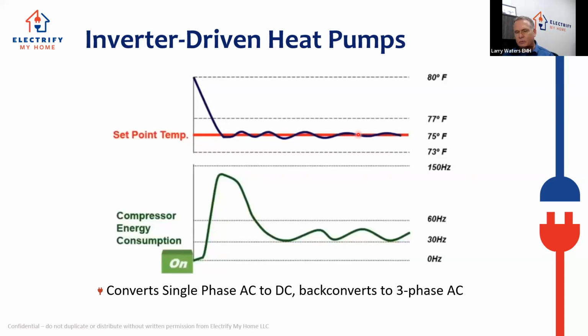And if we just do the math really quickly on this, I can run this system for 6 hours in this for every 1 hour of trying to get the house warm or cool. So with a properly installed heat pump system, it's going to take less toll on your battery, less toll on the solar, and less needed solar overall. So when you combine a solar and battery project with one of these systems, you can actually save the customer a couple dollars on that part, and then switch them over to a system that's going to more efficiently utilize that power that you're generating and storing.